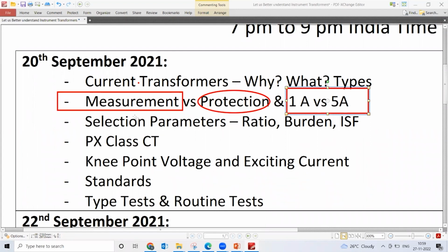Nimesh, burden will decrease, which will need less winding. Burden will decrease, which will need less winding. Not really true. If you're selecting 1 amp, the required burden will come down. But if you're comparing a 100 bar 1, 10 VA CT versus a 100 bar 5 with the same 10 VA rating, obviously your 1 amp will be bulkier, right?